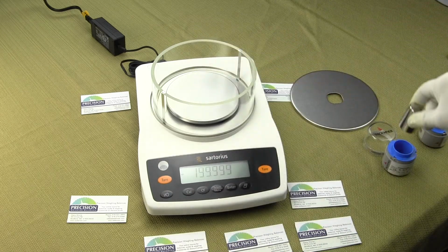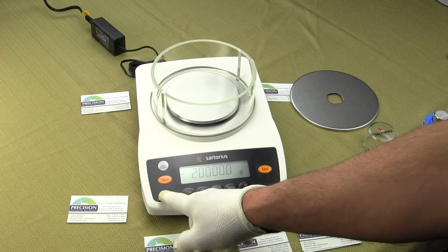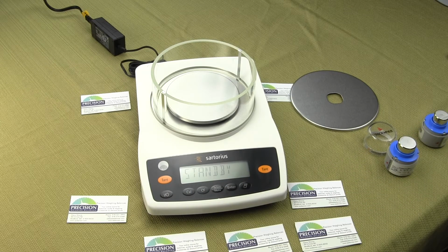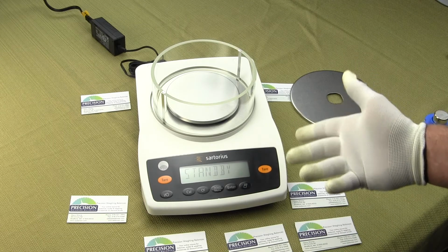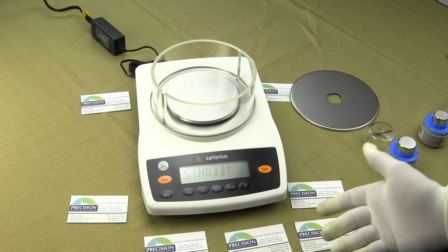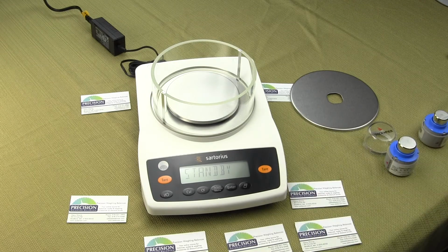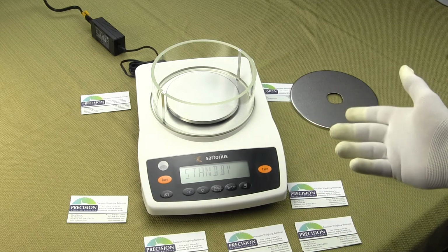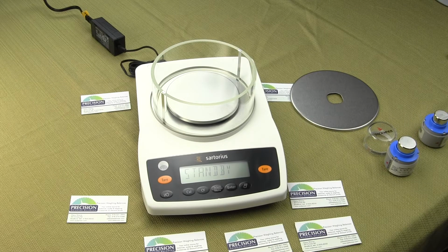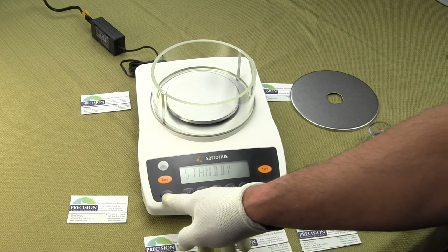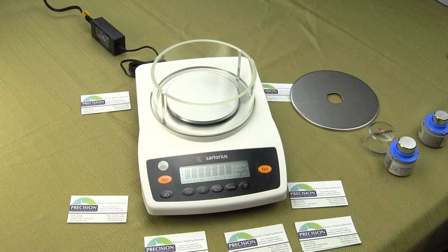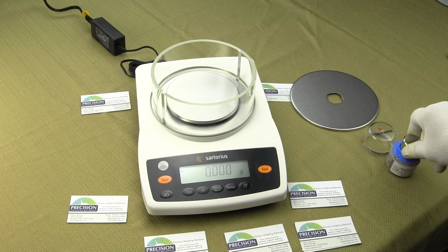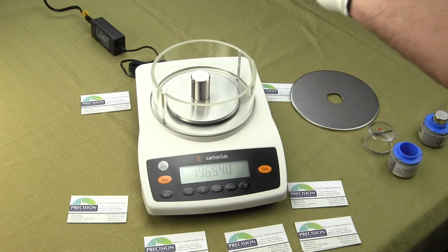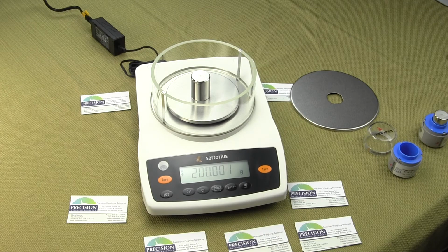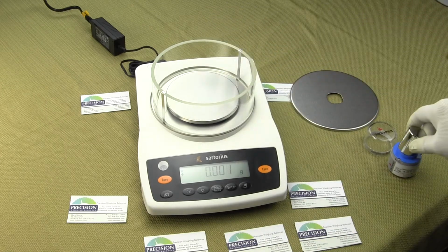So take the cal weight off. If I was to shut off the balance, you'll notice the balance says that it's in standby. So this is what we recommend. If you're not using the balance, leave the balance plugged in, but always have it in standby mode. So that way there's a small trickle current going through the electronics, and the electronics are all warmed up. To start the balance up, simply press that button and you'll see the balance goes through a power up sequence really fast and then goes right to 0.0. Place the weight on the balance. And you can see how quick the response time is.